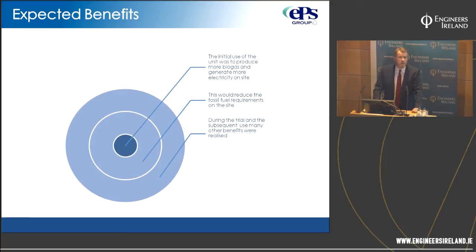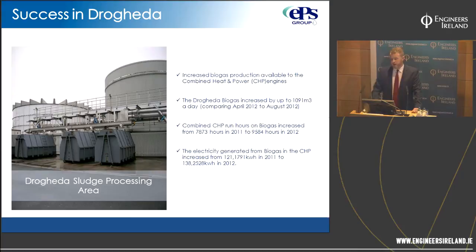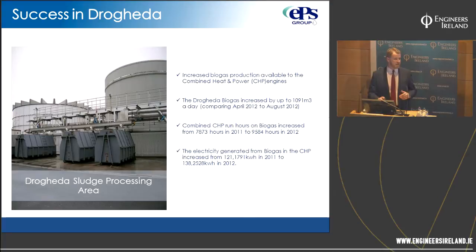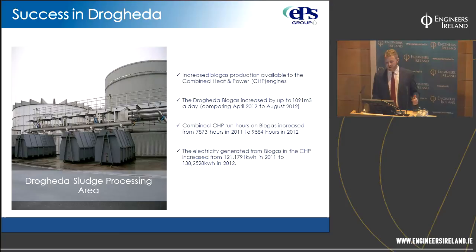What were we hoping to gain? Simply, to produce more biogas — reducing our reliance on fossil fuels, both electricity on site and natural gas. During the trial, many other benefits were realised, some of which we had underestimated. In terms of biogas production, the Drogheda trial was extremely good — over 30% increase in biogas production on site, with the best case figure at 1,091 cubic metres. On average since operation began in 2012, it's been over 30% additional biogas at that plant.